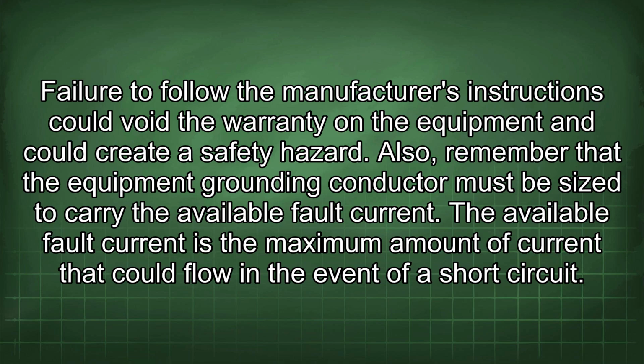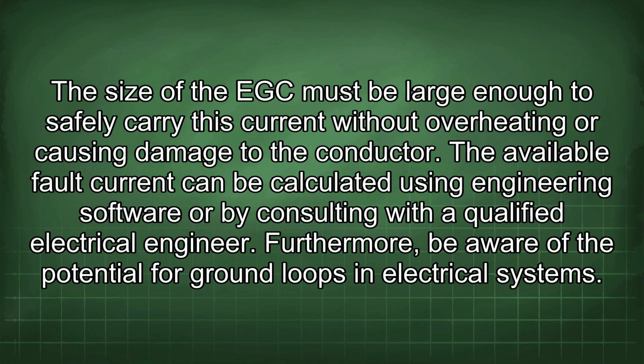Also, remember that the equipment grounding conductor must be sized to carry the available fault current. The available fault current is the maximum amount of current that could flow in the event of a short circuit. The size of the EGC must be large enough to safely carry this current without overheating or causing damage to the conductor. The available fault current can be calculated using engineering software or by consulting with a qualified electrical engineer.